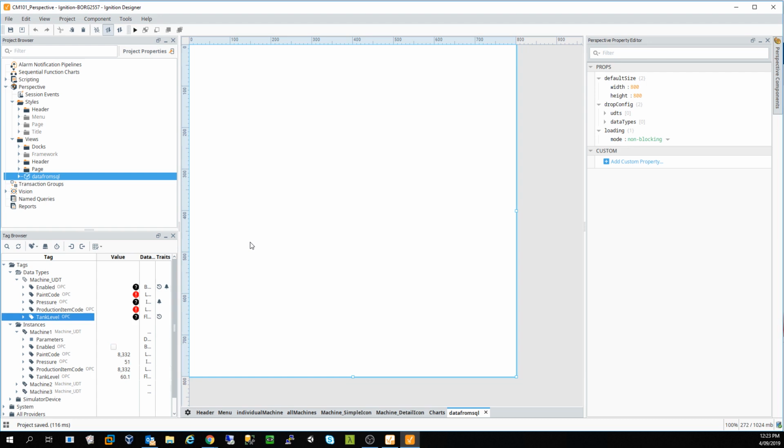named queries, so the predefined equivalent of, say, stored procedures on the database side of things. We can create our own SCADA-based stored procedure type functionality with named queries, or we can query directly, or we can write script in Python, the native scripting language, that will directly access those data sources using system level drivers, or we could write our own database from scratch using whatever mechanism we wanted. We could even write custom drivers to talk to bespoke equipment in those scripting languages.